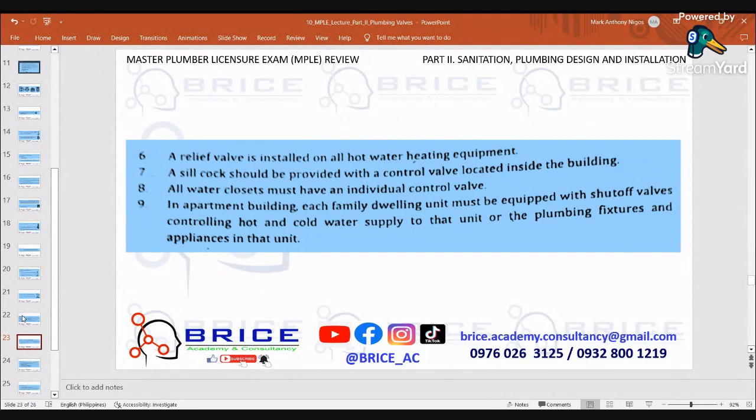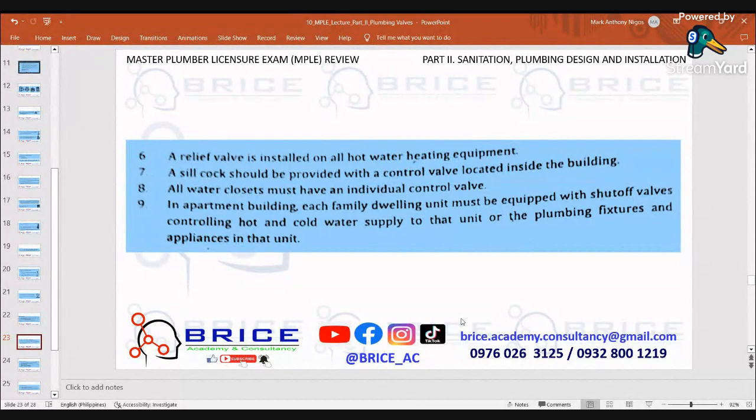Number 6, a relief valve is installed on all hot water heating equipment. Number 7, a sillcock should be provided with a control valve located inside the building. Number 8, all water closets must have an individual control valve. Number 9, in an apartment building, each family dwelling unit must be equipped with shut-off valves controlling hot and cold water supply to all of the plumbing fixtures and appliances in that unit.